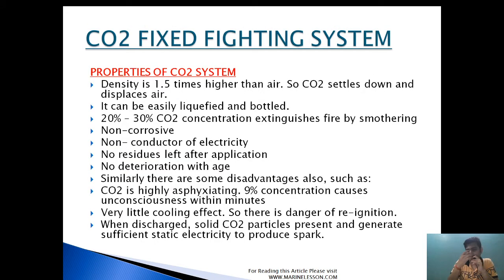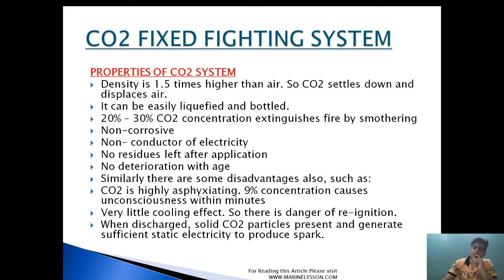Very important point — what are the properties of CO2? These are asked in MMD Class 4. The density of CO2 is 1.5 times higher than air, so CO2 settles down and displaces air, performing smothering action. CO2 can be easily liquefied and bottled. A 20 to 30 percent CO2 concentration extinguishes fire by smothering action — as CO2 is heavier than air, it settles down and forms a blanket over equipment, preventing the fire from sustaining. CO2 is non-corrosive in nature, a non-conductor of electricity, and leaves no residue after application.